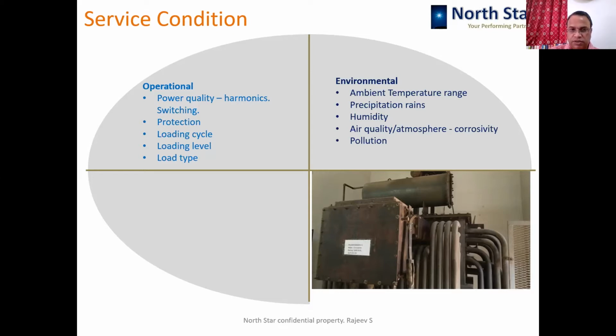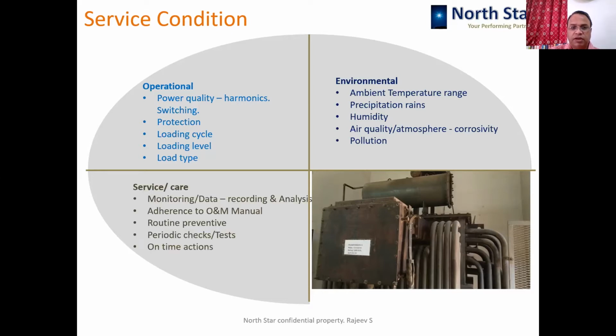Of course, all these parameters are taken care of while placing the order of the transformer. So that must be taken care of when the transformer is being procured. And then the routine operation and maintenance of the transformer, which comes under service care, like regular monitoring of data, recording, analysis, adherence to the O&M manual, routine preventive maintenance, periodic checks, which we are going to cover today, and on-time action. This transformer, which is being shown over here, is purposely shown. It is a very old transformer. It is 60 years old and it is still working quite satisfactorily. Though the appearance is not good, you can see it is not dirty or oily or leaking from any place. So that way it is maintained very nicely.